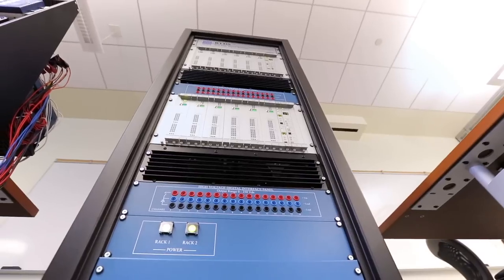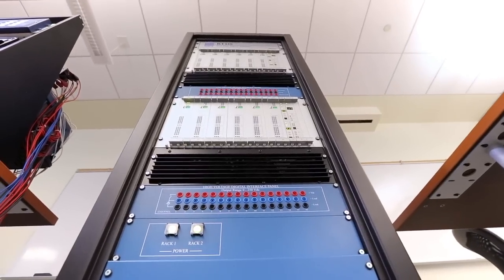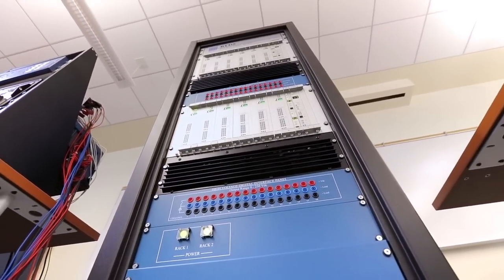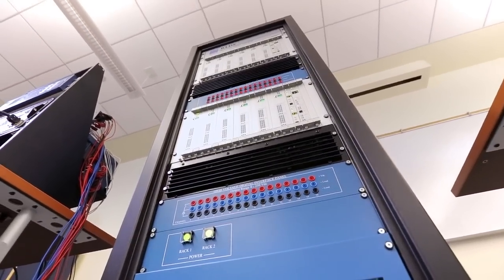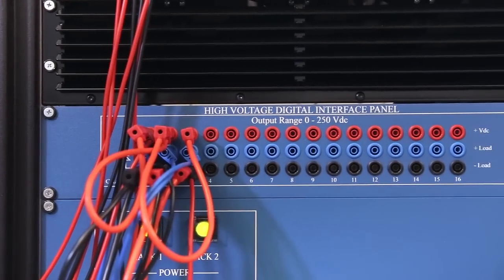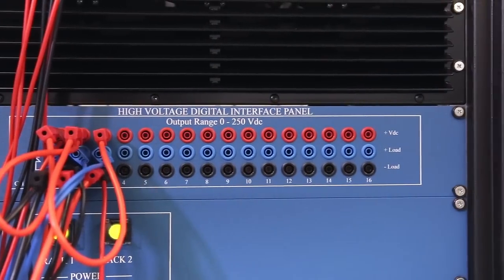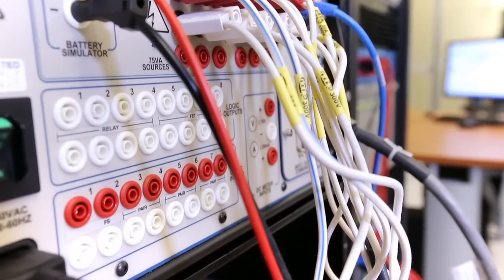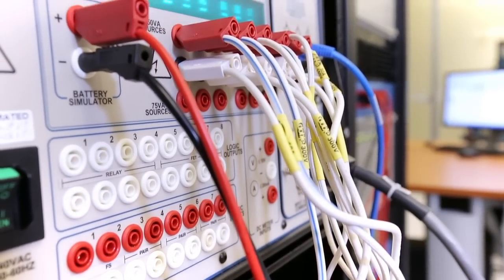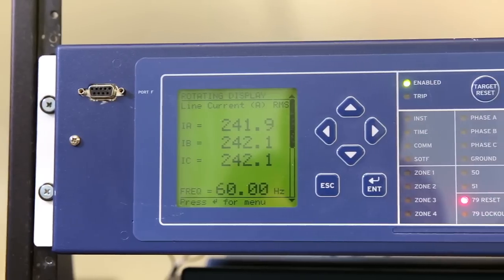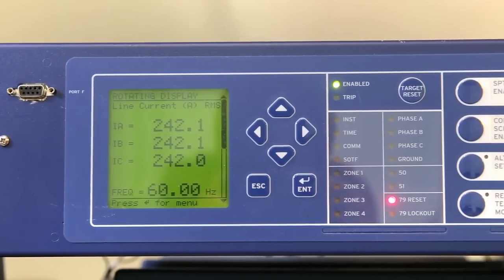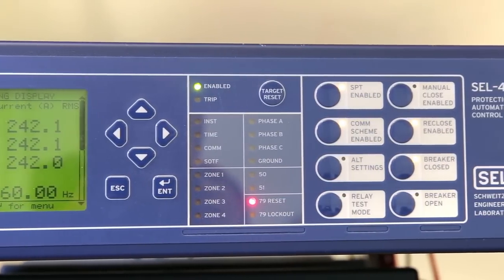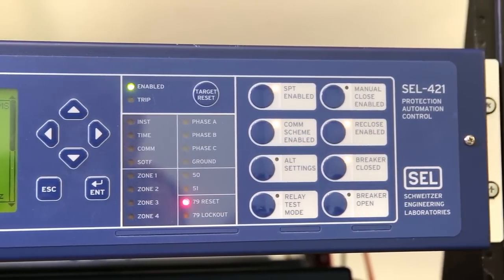The high voltage panel component is used to define signals to be communicated via the high voltage digital output panel mounted in the RTDS simulator cubicle. This panel is capable of switching at station level voltage and here it's used for breaker status signals.